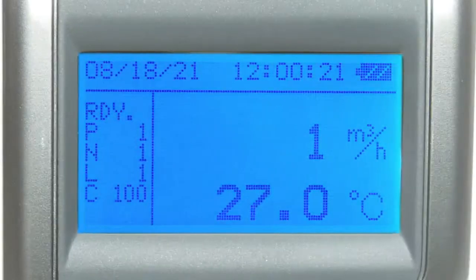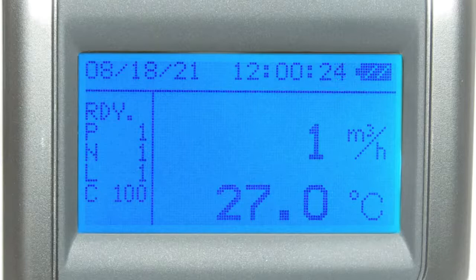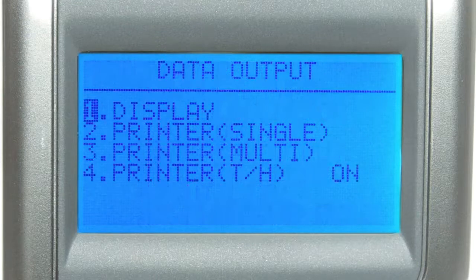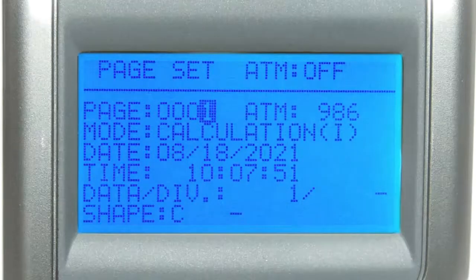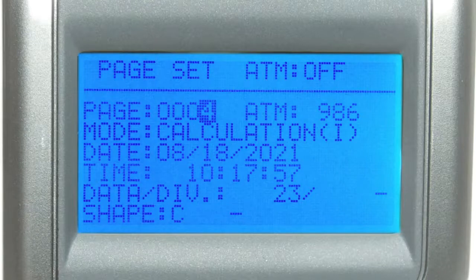The data that gets stored on the Climomaster during calculation mode and flow rate mode is dependent on the model of the probe you used for measuring. For example, if you used probe model 6541, it would be impossible for humidity data to be stored due to it lacking the functionality to sense humidity. If you want to recall stored data, all you have to do is navigate to the Data Output section in the main menu. By selecting Display, you'll be brought to the device's database where you can select pages displaying every bit of data from previous measurements. The mode, date taken, time taken, each individual parameter you configured for that test, and each sample and/or location's results. You can also filter through the different modes used by pressing the Mode button.